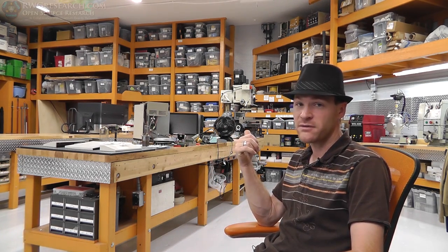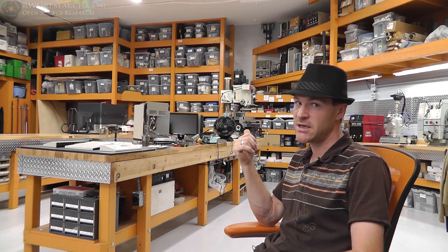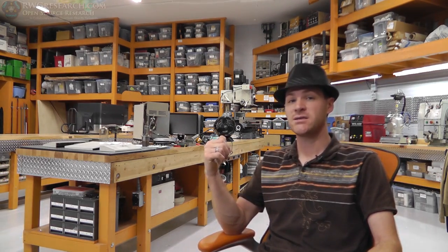I actually had to grind off some of the very small epoxy on those thermocouple wires, kind of sketchy stuff. If I nip one of those, they go into that cell, the whole thing is shot. So it's a little bit of a tedious, delicate process. So the idea here is exactly what I explained - to make a pressure closed cell with a working DSC.